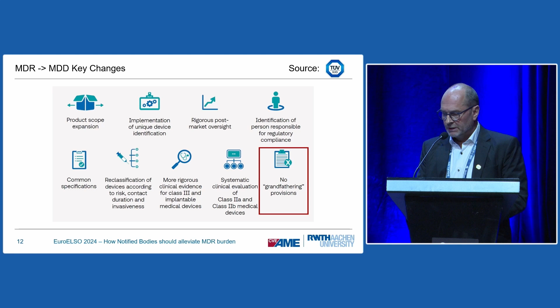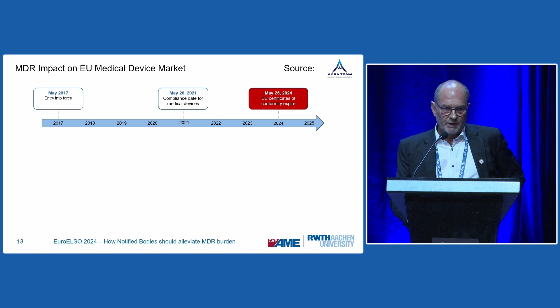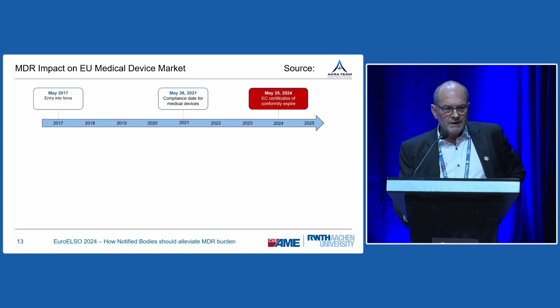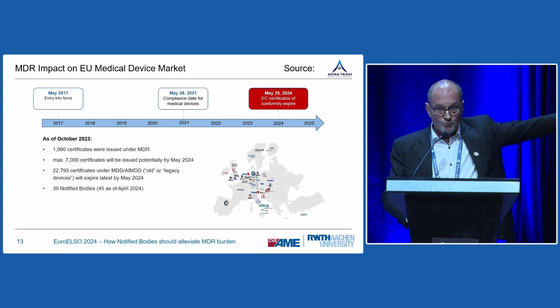I would like to point out two or three things. For example, one is no grandfathering provisions, because it is very important to understand what happened here. Basically, all medical devices now have a certificate for a maximum of 5 years, and all the old or legacy devices had to be reclassified. That means devices that you had been working with, for example, heart valves. I remember the St. Jude heart valve, on the market since 1977, implanted millions of times, suddenly needs to be recertified. And that has to be done, by the way, until May 25, 2024. Looking at the date, that's just in one month.